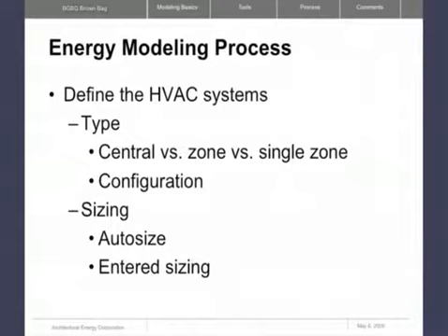Commonly, when we're doing a LEED analysis, we use auto-sizing because as we do various energy conservation measures, the load on the building changes, and so the sizing should change. And we want the program to calculate that sizing. And so one of the outputs that we get is, well, if you do all these things, not only do you save energy, but you can put in 10 times less cooling.